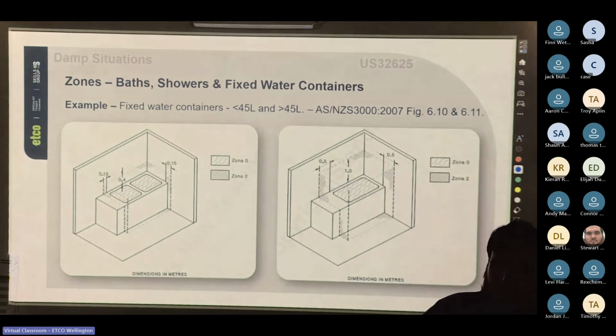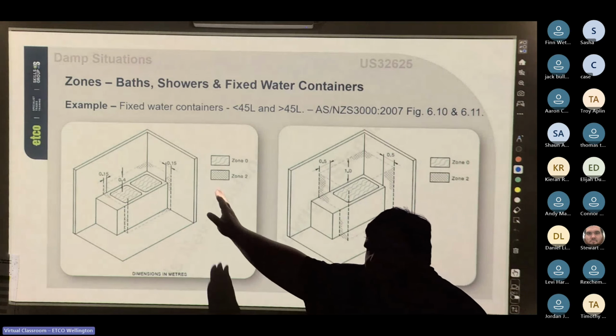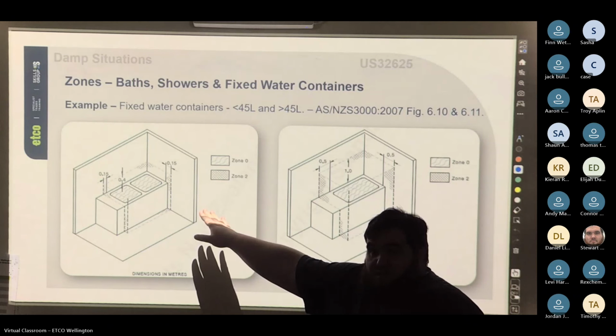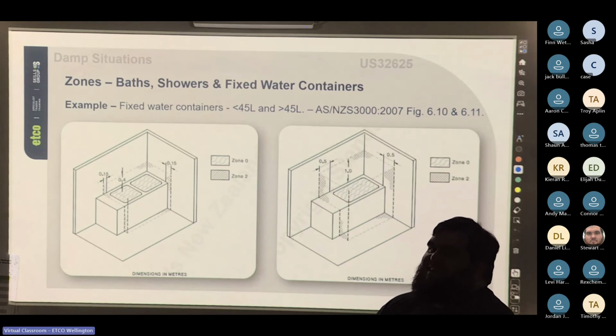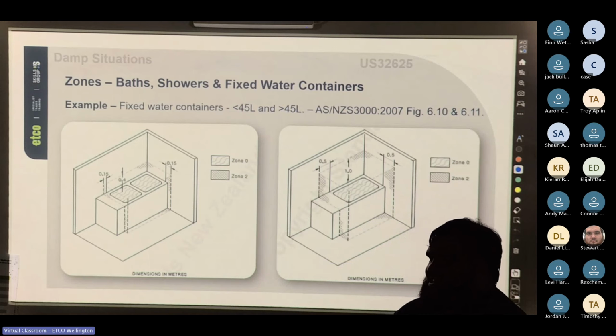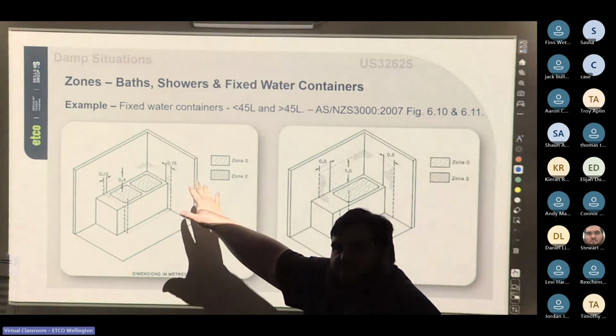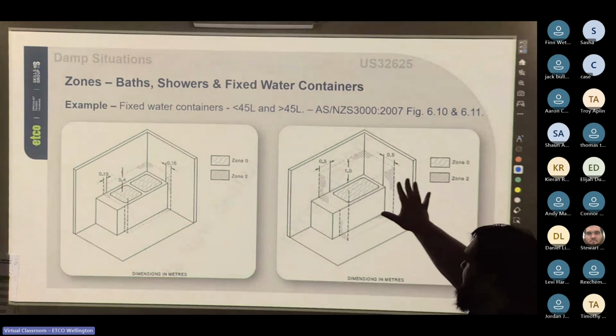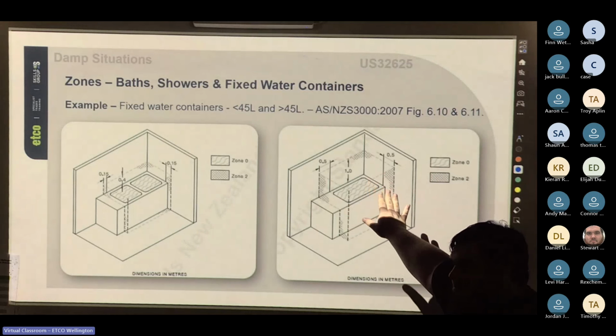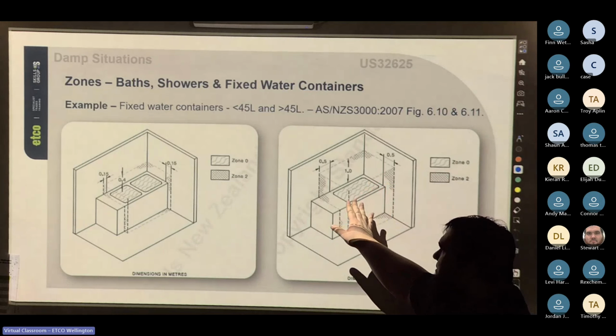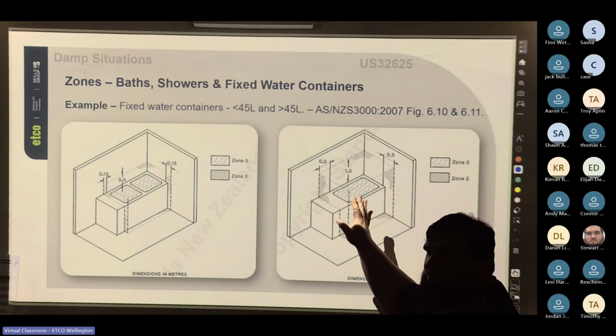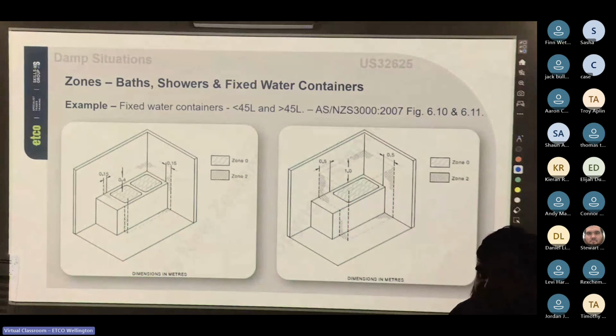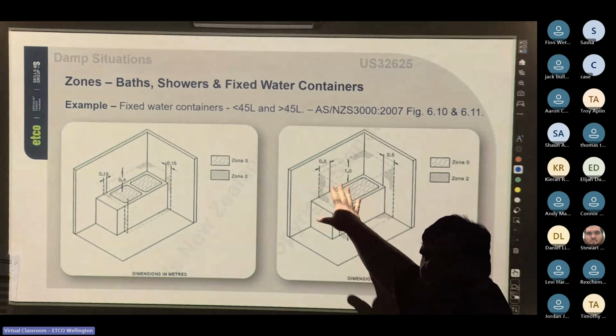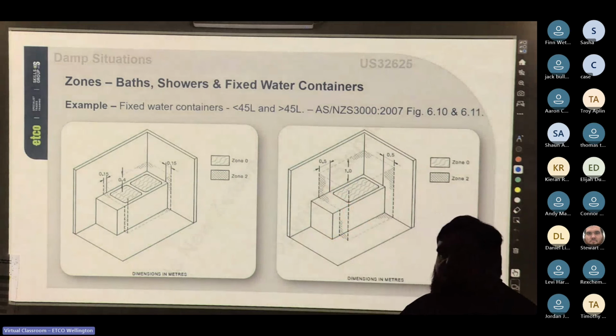But in my personal viewpoint, I ignore this one. Yes, amen to that, Sean. So I would never follow this measurement. I would be more comfortable with this, but my preference for a PowerPoint or a light switch near a water container of this size, I want to probably be at least 750 or more away from the water container. Again, this is the minimum safe distance as per 3000, but you can go beyond that.